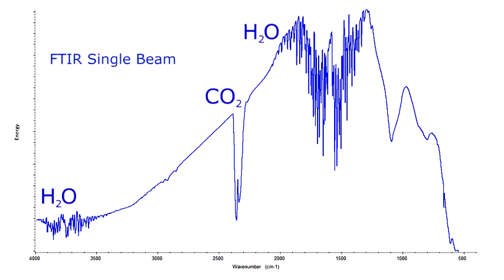Here we observe water vapor and carbon dioxide absorbances, which is expected when the sample compartment is not purged.